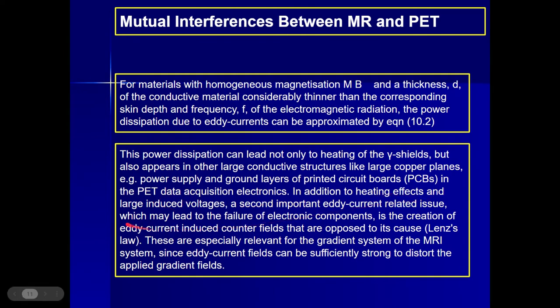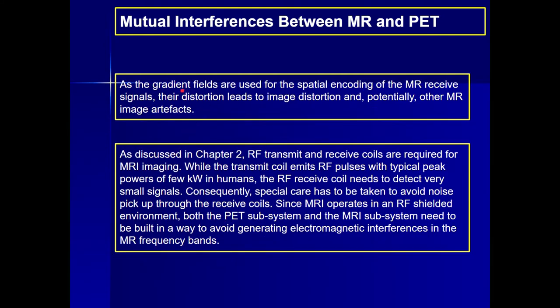In addition to heating effects and large induced voltage, a second important eddy current related issue which may lead to failure of electronic components is the creation of eddy current induced counterfields that are opposed to their cause, Lenz's law. These are especially relevant for the gradient system of the MRI systems, since eddy current fields can be sufficiently strong to distort the applied gradient fields. As the gradient fields are used for spatial encoding of the MR received signals, their distortions lead to image distortions and potentially other MR image artifacts.